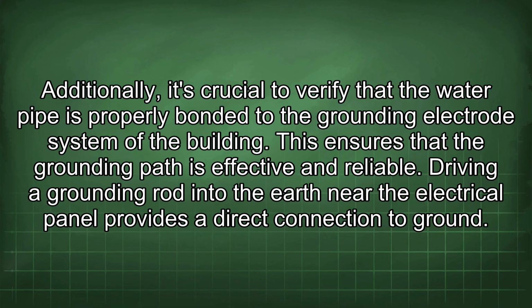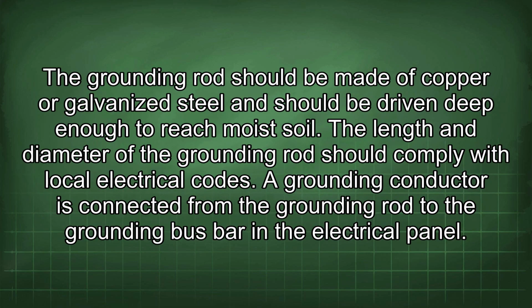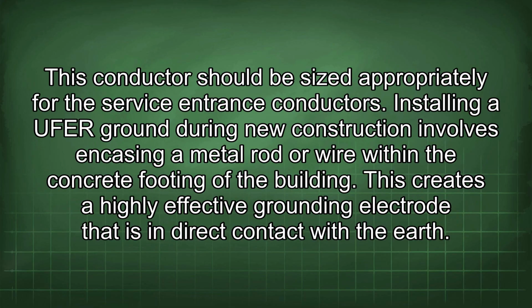Driving a grounding rod into the earth near the electrical panel provides a direct connection to ground. The grounding rod should be made of copper or galvanized steel and should be driven deep enough to reach moist soil. The length and diameter of the grounding rod should comply with local electrical codes. A grounding conductor is connected from the grounding rod to the grounding bus bar in the electrical panel. This conductor should be sized appropriately for the service entrance conductors.